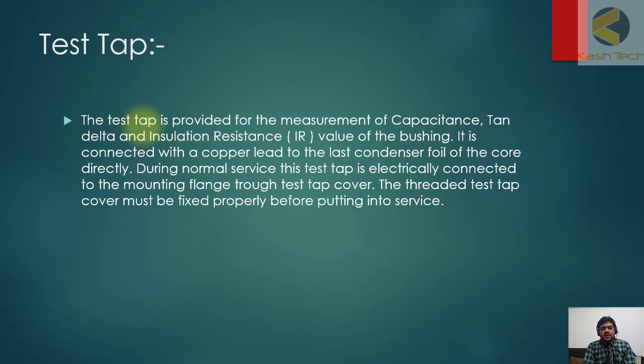Another important thing is the bushing is given with the test tap point. The test tap is provided for measurement of capacitance, tan delta, and insulation resistance values of the bushing. It is a point which is called a tap point during testing.